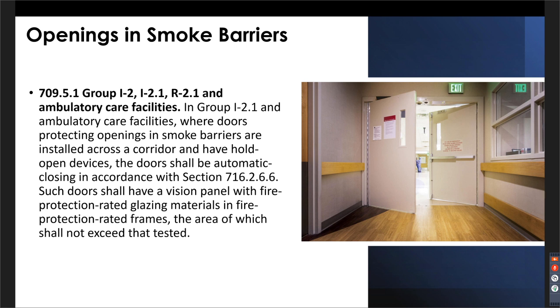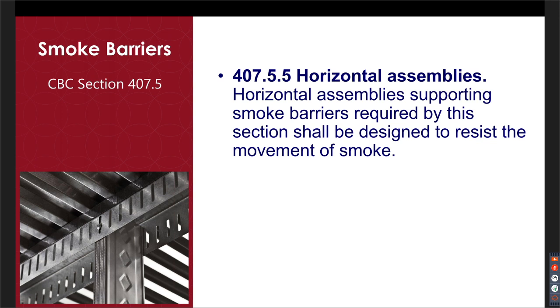So what does that section say? Again, for the I-2s, R-2.1s, and ambulatory care, where doors protecting openings in smoke barriers are installed across a corridor and have hold open devices, the door shall be auto closing in accordance with 716.2.6.6. The doors have to have vision panels with fire protection rated glazing materials in fire protection rated frames, the area of which shall not exceed that tested, and they're opposite swinging.